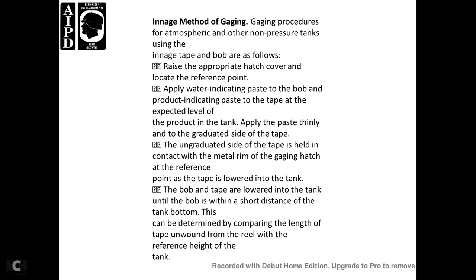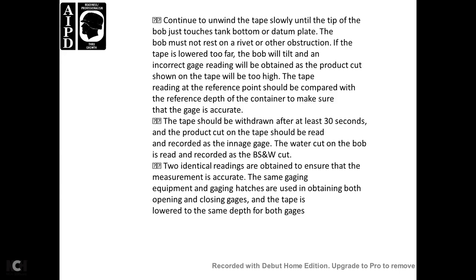Keep the tape in contact with the metal rim of the gauging hatch at the reference point. Lower the bob of the tape to the lower end of the tank until the bob is within a short distance of the tank bottom. This can be determined by comparing the length of the tape unwound from the reel with the reference height over the tank.